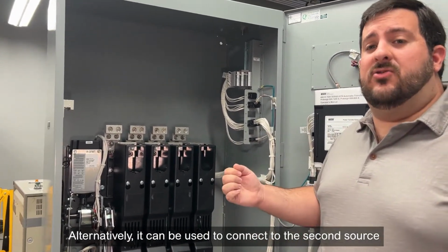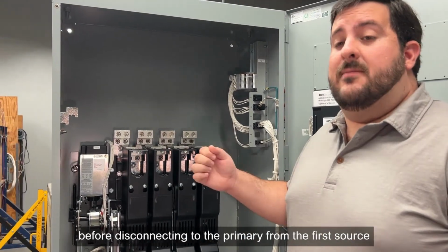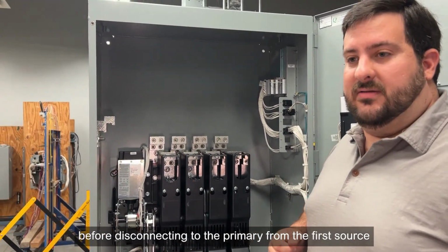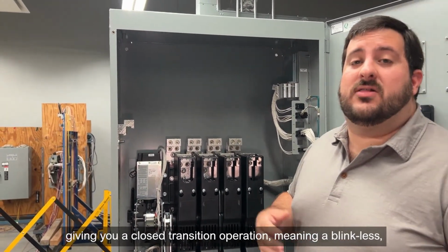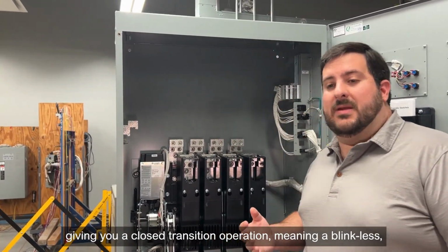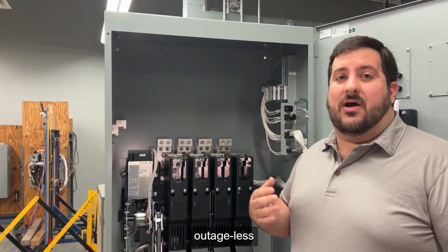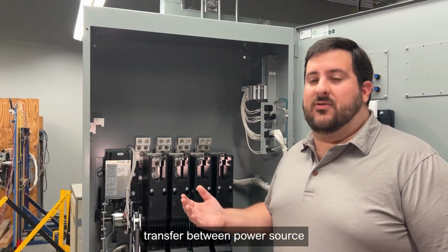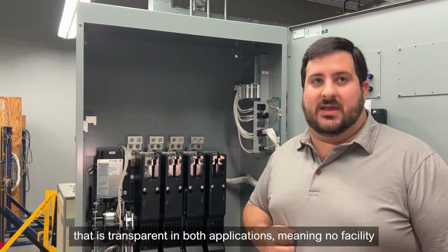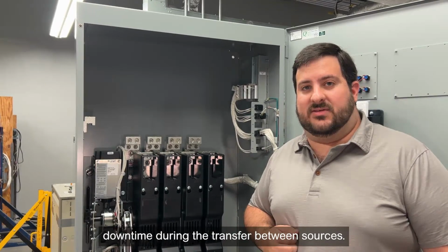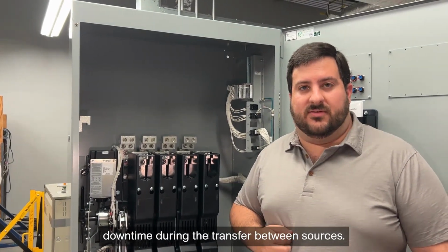Alternatively, it can be used to connect to the second source before disconnecting from the first source, giving you a closed transition operation, meaning a blinkless, outage-less transfer between power sources that is transparent in most applications, meaning no facility downtime during that transfer between sources.